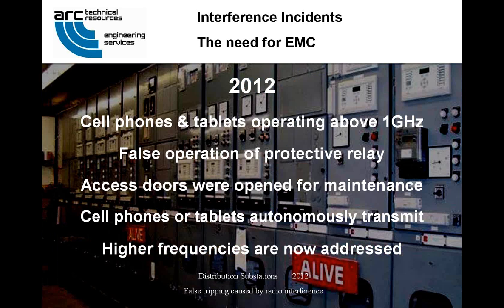The advent of cell phones and tablets operating above a gigahertz, at frequencies above these older IEEE standards, means new RF hazards have now arisen. There have been reports of false operation of protective relays when the access door was open for maintenance, when somebody's nearby cell phone or tablet autonomously transmits. This testing gap at higher frequencies was just recently addressed in IEEE 1613.1-2013, which we'll talk about, for the EMC testing of utility communications networking equipment.